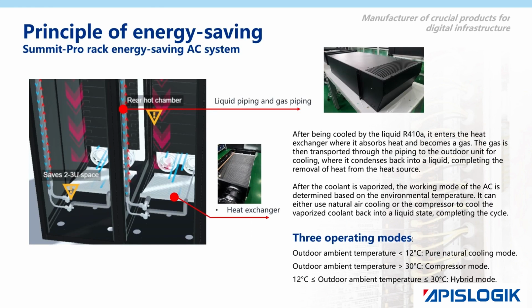The Summit Micro DC is equipped with the Summit Pro rack-mounted energy-saving precision air conditioning system. It uses R410A for cooling. After the refrigerant cools down, it enters the heat exchanger where it absorbs heat and transforms into a gas. It is then transported through the piping to the outdoor unit where it is cooled back into a liquid state, completing the removal of heat from the heat source.